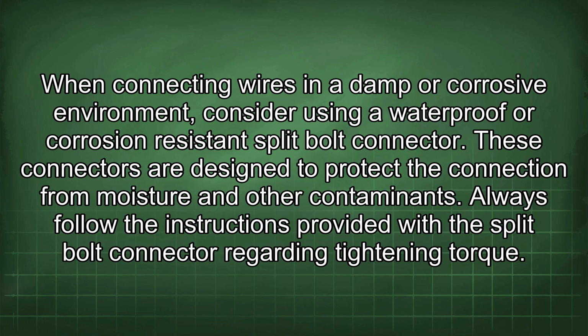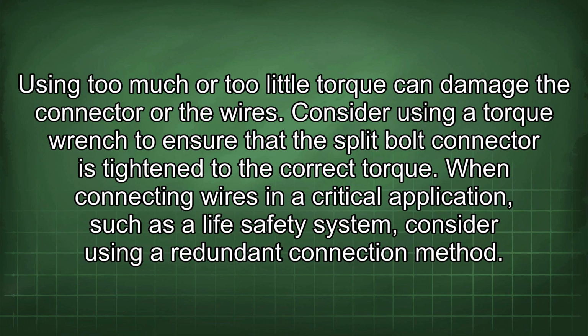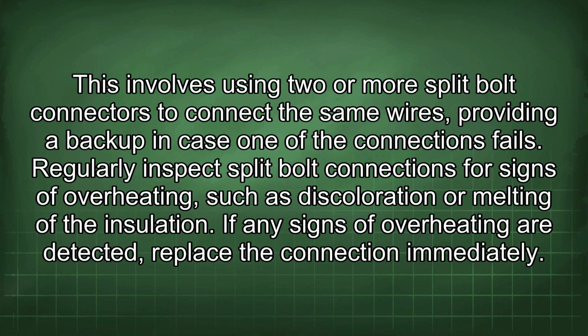Always follow the instructions provided with the split bolt connector regarding tightening torque. Using too much or too little torque can damage the connector or the wires. Consider using a torque wrench to ensure that the split bolt connector is tightened to the correct torque. When connecting wires in a critical application such as a life safety system, consider using a redundant connection method. This involves using 2 or more split bolt connectors to connect the same wires, providing a backup in case one of the connections fails.